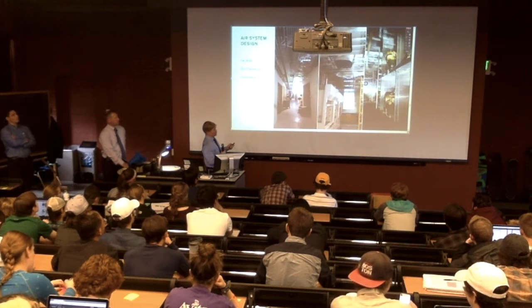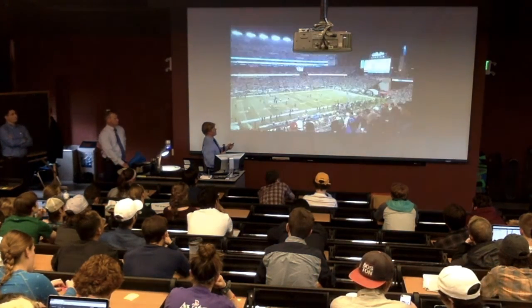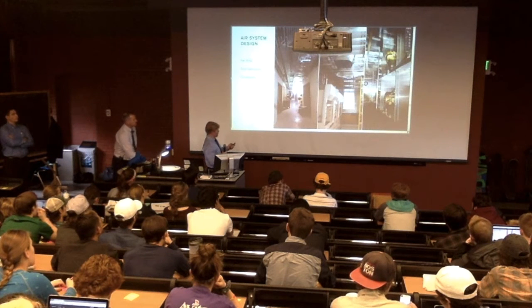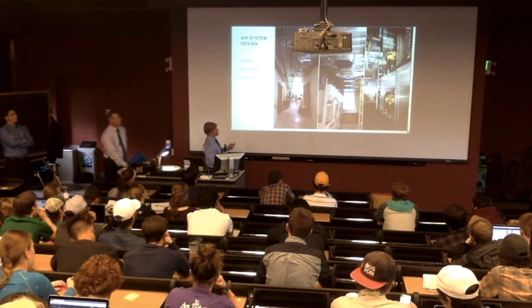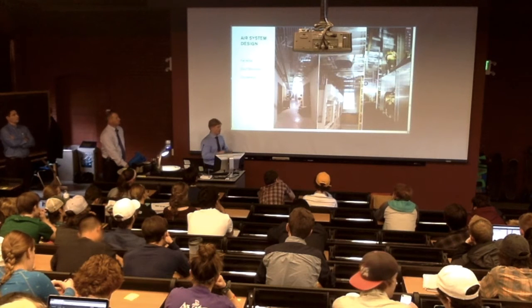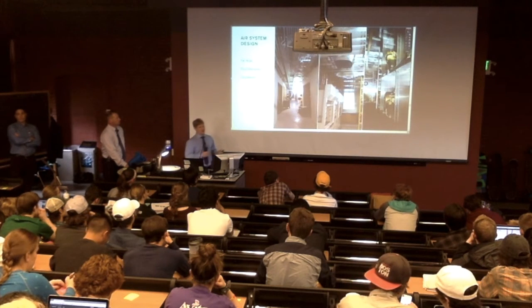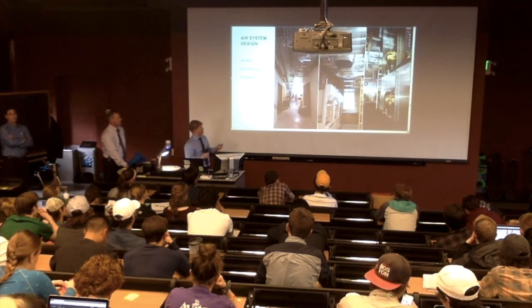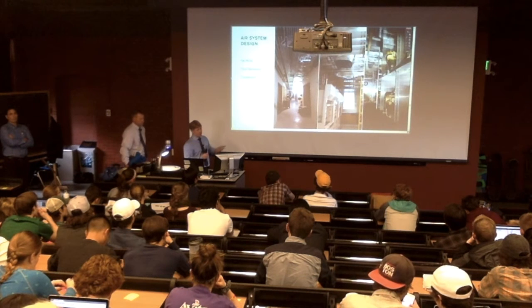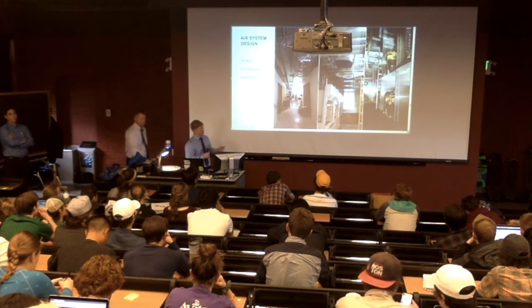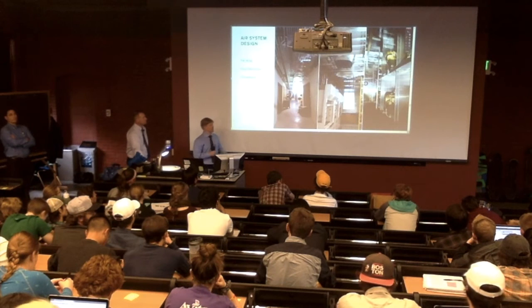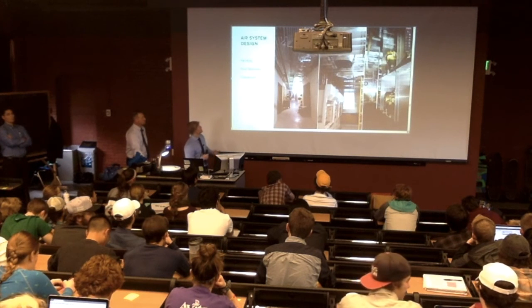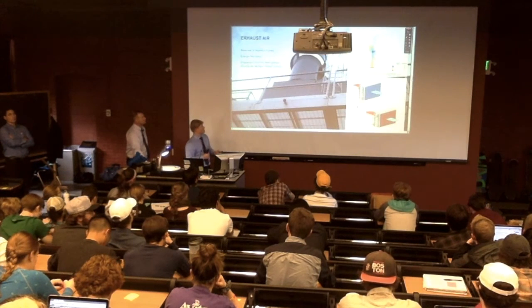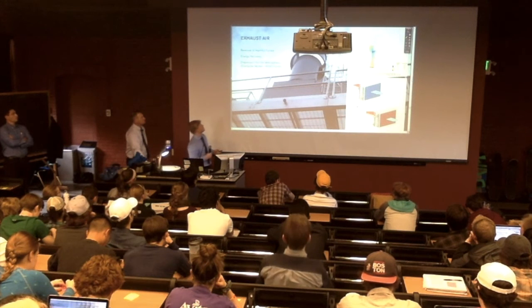In the model walkthrough I was showing you before, this is the main supply duct down the corridor. That model doesn't even show all the conduits that end up getting thrown up there after the fact. We don't actually model every half-inch conduit, but that's what's required to run the lighting in all the spaces. And if we don't draw it, we need to account for that space to fit in above the ceiling. So that's some of the stuff we do on the supply side.